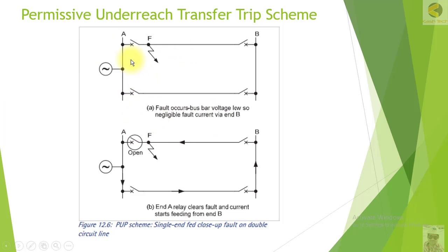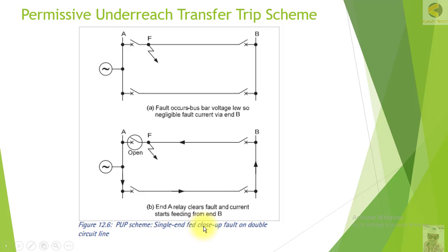This example shows a generating source at one end only. If there is a fault nearest to Station A, the fault will be fed by Station A because this is the shortest path, and there will be negligible current through Station B since that path is very long. Once the breaker at A opens, fault current will then be fed from Station B. This is the PUTT scheme example with single-end infeed on a double circuit line.